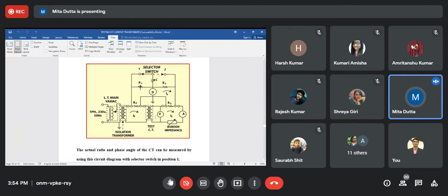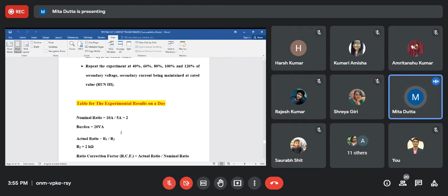Now, first, when we are performing the test, we will first find out ratio error at rated secondary current and rated secondary voltage. Now, from the nominal ratio, we have seen that the rated secondary current is 5 ampere. And since this is the rated burden, so the burden will be the rated secondary terminal voltage into rated secondary current. And so when we divide 20 VA by 5, we will get 4 volt. That will be the rated secondary terminal voltage, and rated secondary current is 5 ampere. That is why here in first run, this is run 1, this is run 2, and this is run 3. So we have 5 ampere secondary current, we have 4 volt VS. So rated IS and VS.